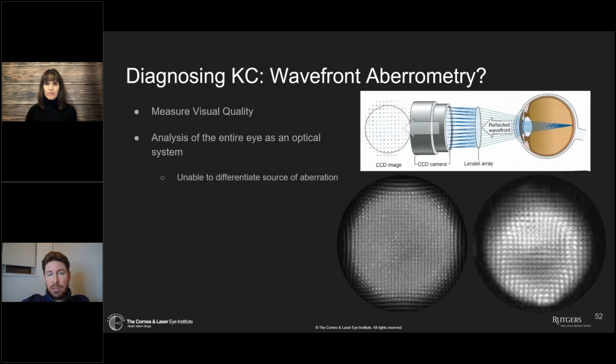The way that this technology works is we project light into the eye and we watch the reflected light coming back out of the eye. That reflected light hits a micro lenslet array. You can imagine a micro lenslet array being almost like the eyes of an insect, where you see those multiple little lenses. What you're getting is that light hits that and it focuses to individual points on a sensor. And these are the sensor images that you'll see.